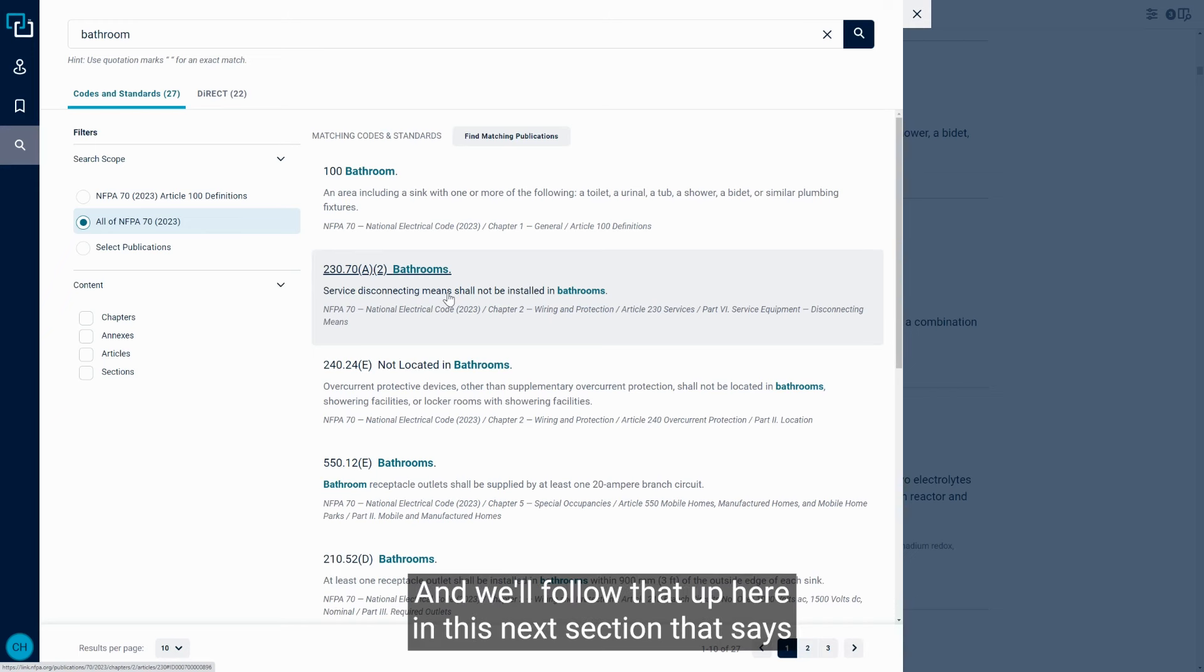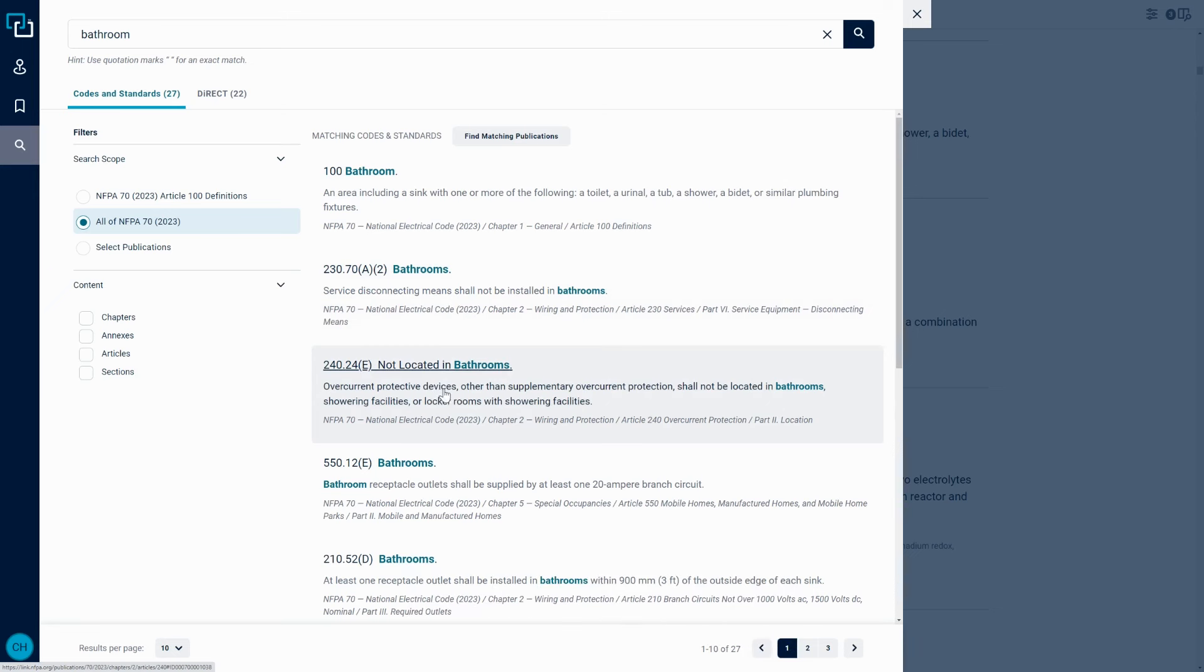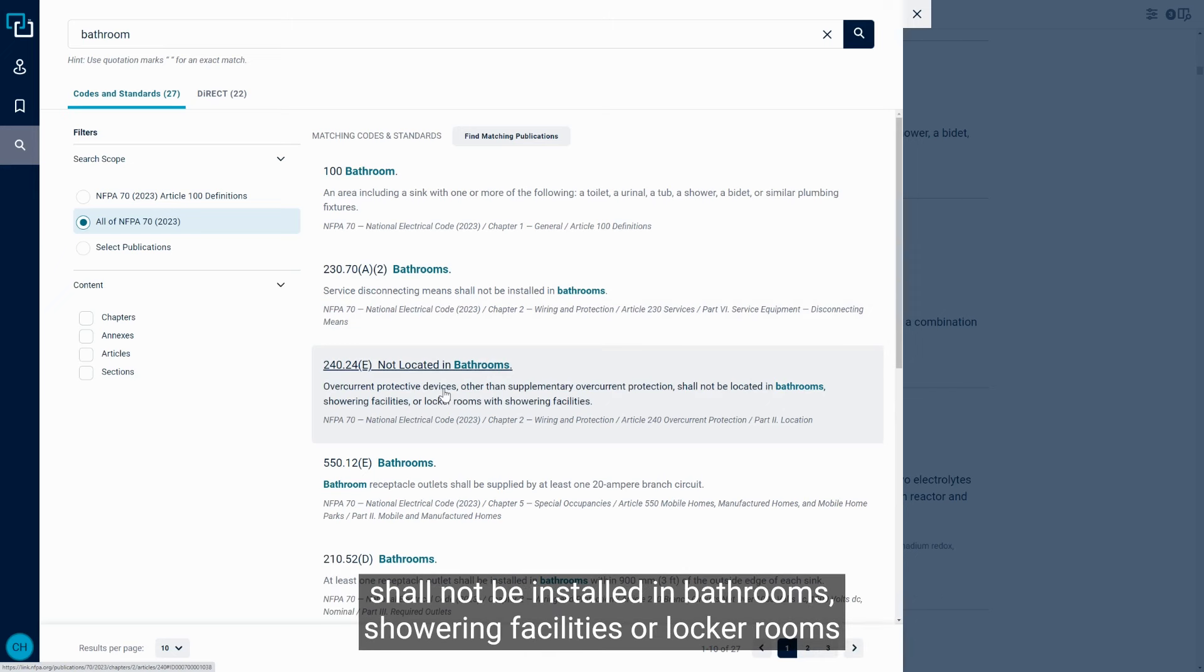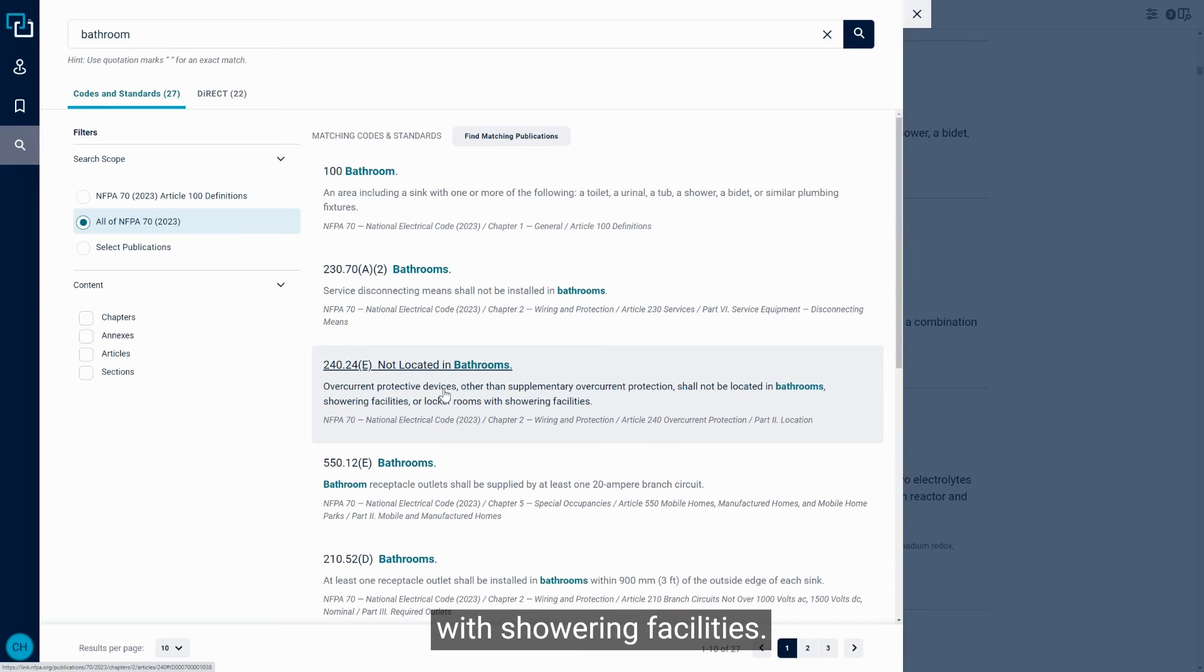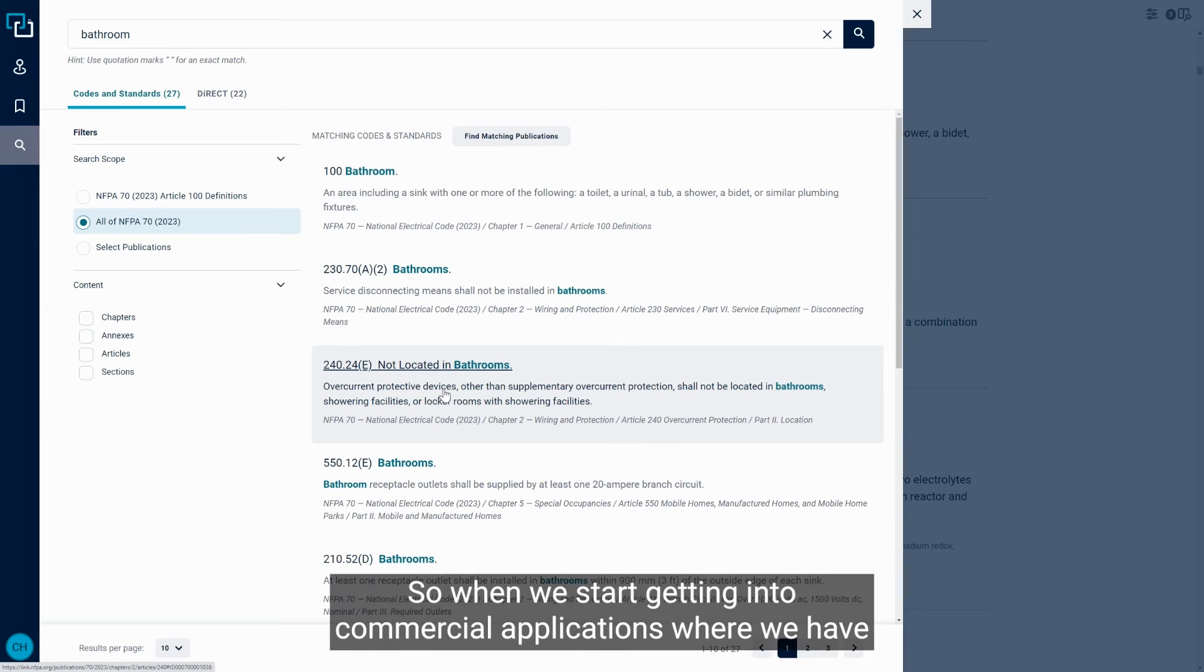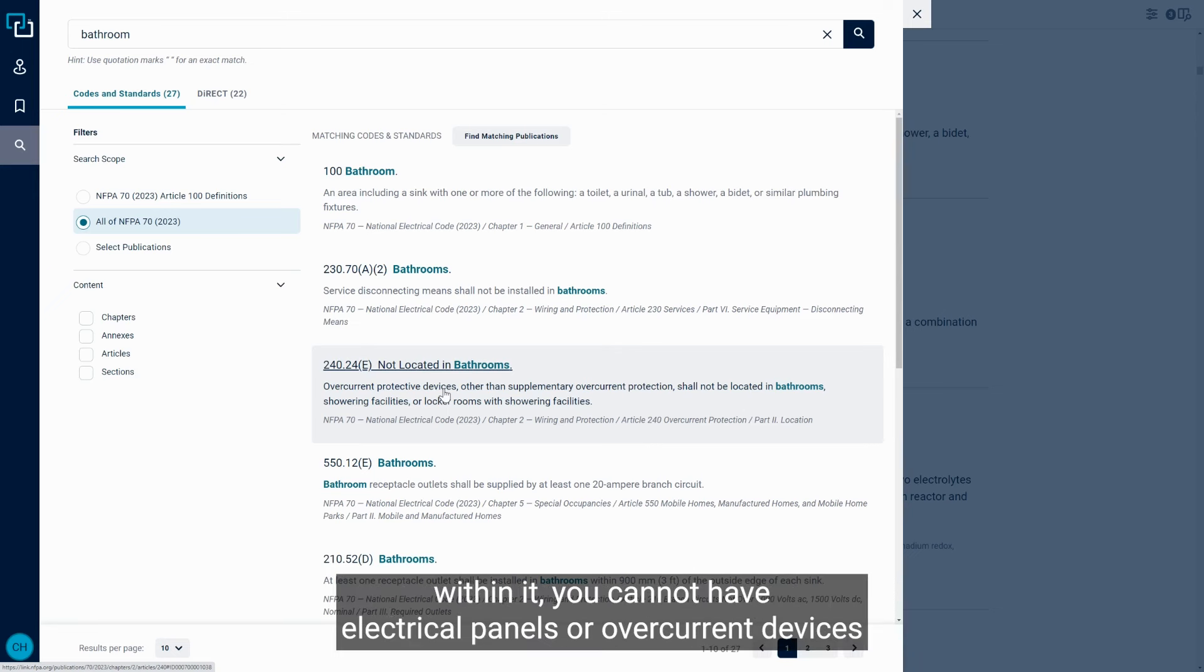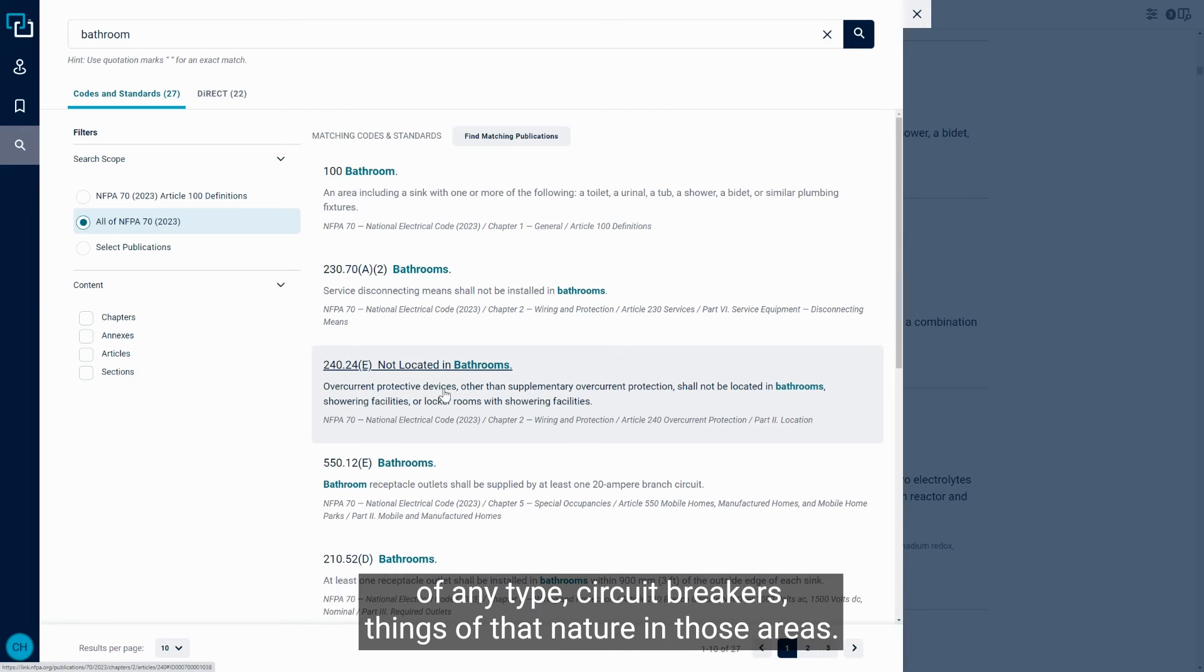And we'll follow that up here in this next section that says 240.24.E says overcurrent protective devices, other than supplementary overcurrent protection, shall not be installed in bathrooms, showering facilities, or locker rooms with showering facilities. So when we start getting into commercial applications where we have locker rooms, maybe in a gym, the locker room that has showers within it, you cannot have electrical panels or overcurrent devices of any type, circuit breakers, things of that nature in those areas.